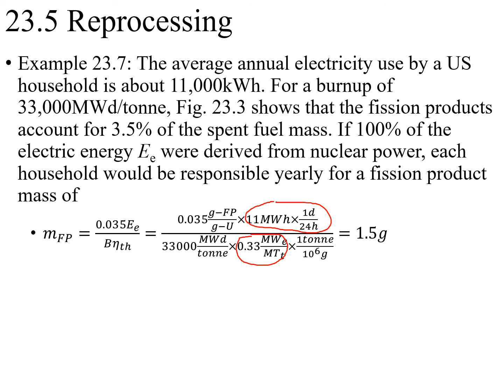This amount of thermal energy is produced by some number of tons of fuel—we divide the total thermal energy by the coefficient of 33,000 megawatt-days per ton to get the total amount of fuel used. Then we multiply by 3.5%, because only 3.5% of that fuel is turned into fission product.